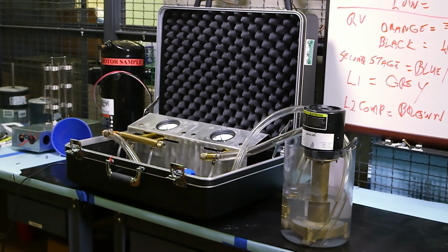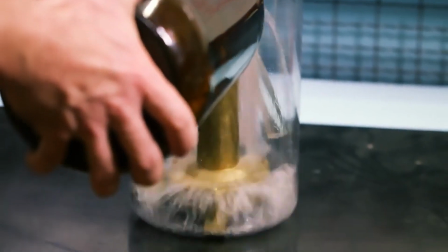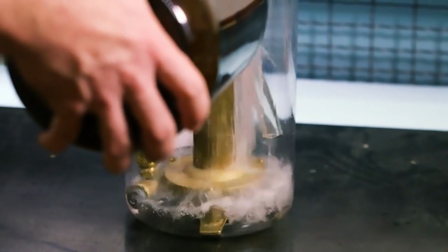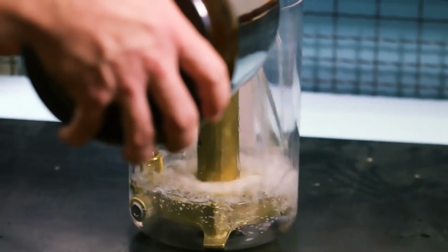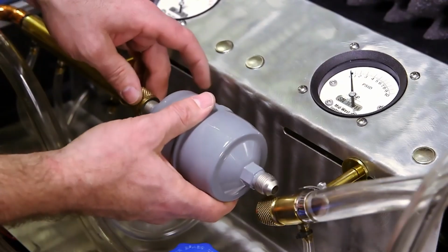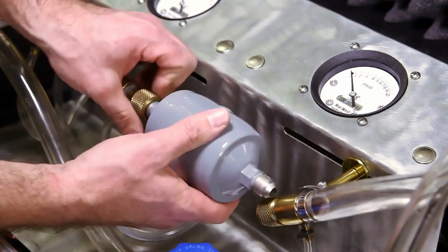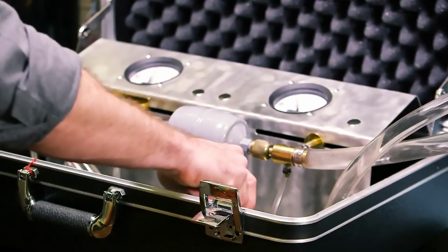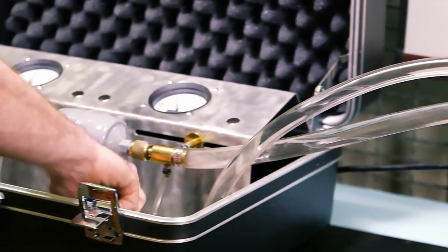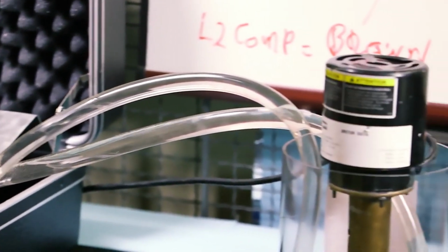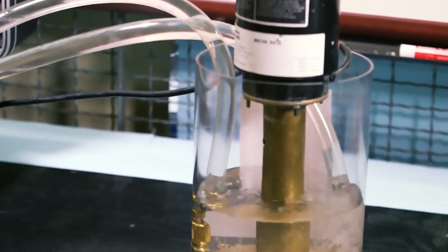This demonstration closely replicates the ASHRAE procedure for testing liquid-line filter dryer filtration by filling the receiver tank with refrigerant. In this closed-loop system, we simulate the conditions present in an air conditioning or refrigeration system. First, we'll install a competitor's solid core filter dryer. Starting up the system, you'll see the liquid refrigerant entering the dryer, passing through it, and then being recycled and pumped back through the system.